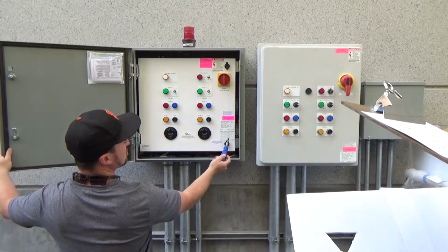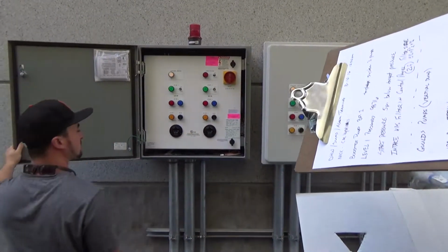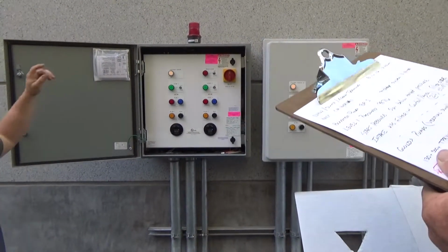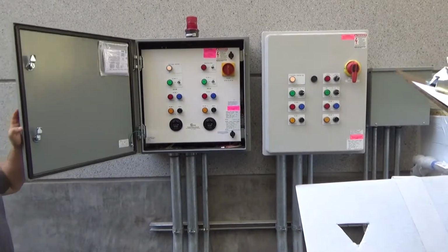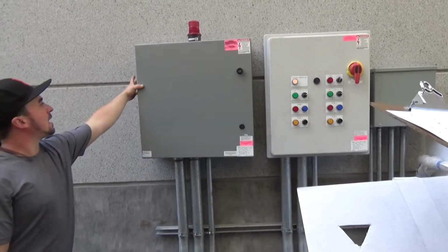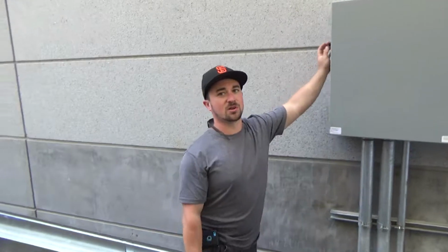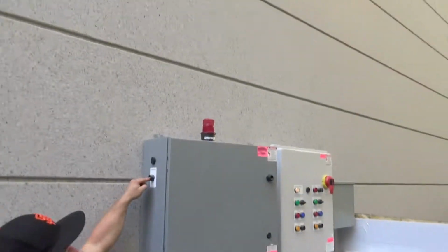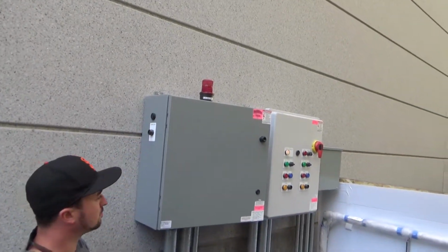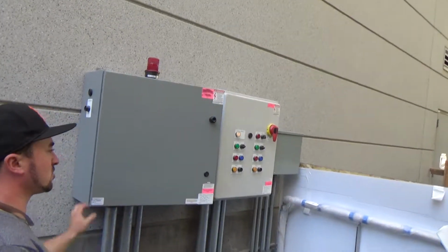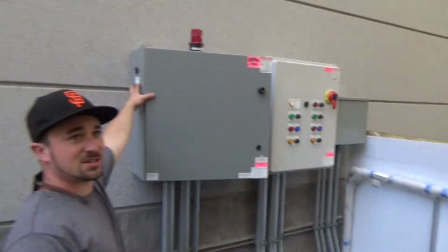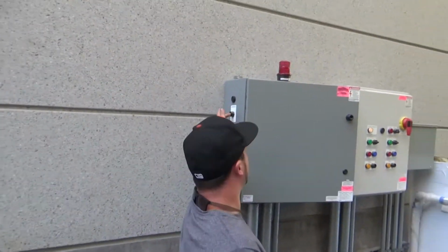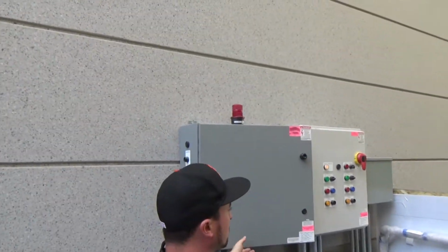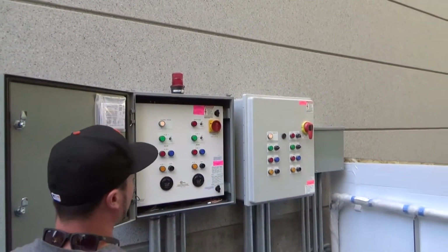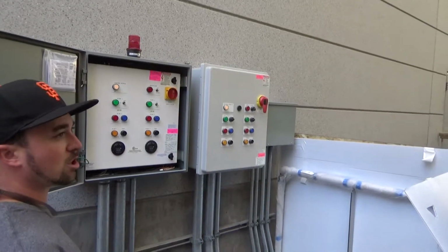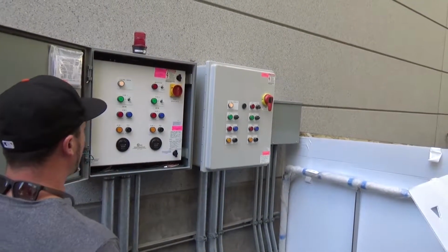This one has the false door, which you would just open up with those tabs. And this one has the LED light on top, which will let you know. And the alarm silence on this one is located on the left side. So you guys get some sort of alarm and it's beeping in your face and you're trying to troubleshoot and you want it to shut up, you would just hold that button down, it'll quiet it, and you can complete your troubleshooting with the panel still on, so you can try to find out what happened.